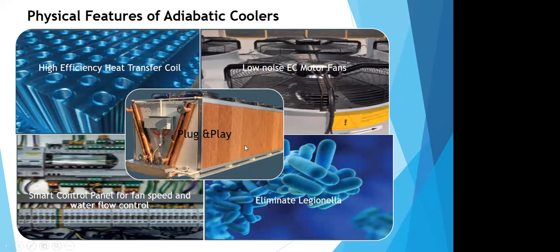And lastly, we do not have accumulation of water, since this is a closed circuit, and the water coming from the condenser of the chiller is in a closed loop. It is not exposed to the atmosphere. It does not fall into a basin, or accumulate, or stagnate. And so the possibility of Legionella formation is virtually zero in this case. Legionella is basically a bacterium which develops in stagnated water, typically in traditional cooling towers which have a basin, and it may cause pneumonia. So we get rid of all those problems.